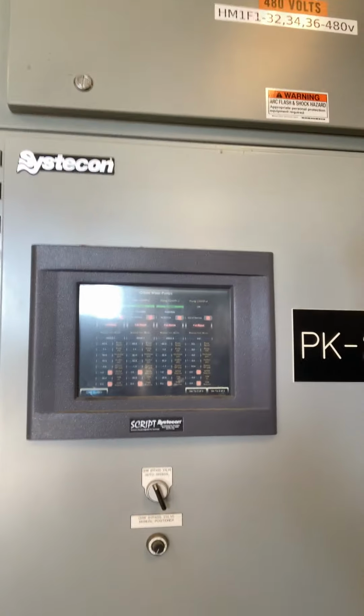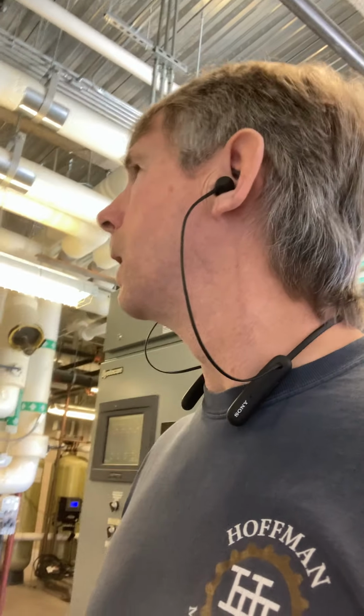out to the system. If I turn around here, I've got another Systecon pumping package. And that one is for the chilled water. That's the cold water being delivered to the building to the air handlers. Alright, so very important that this thing is working properly. So there are pressure transducers that actually measure water pressure on the entering and leaving side of each pump. If one of those fails, that pump is going to shut down. So luckily we do have redundancy here.